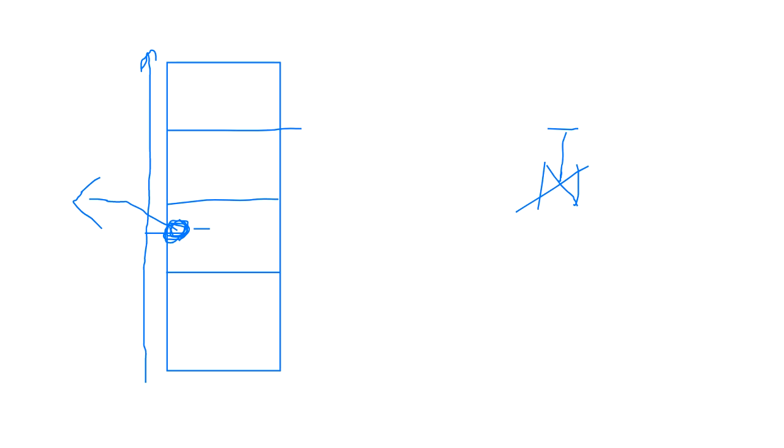The second one: after the fire, they want to maintain the system, right? So this area got the water, and they want to put it in service. They will close this line, discharge the water, and do the maintenance for the surface problem. Or if there is some leakage in this area, you cannot isolate the complete building at any time. So you just close the valve for this line and do the maintenance. This is how a zone control valve is required in a multi-story building.